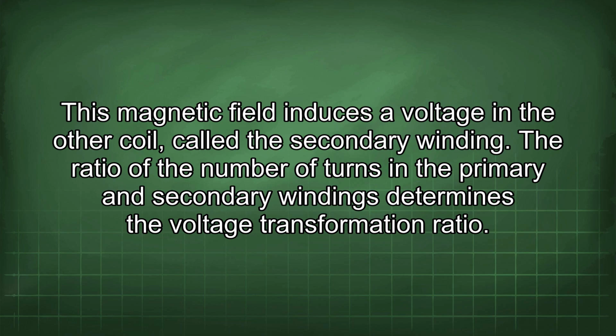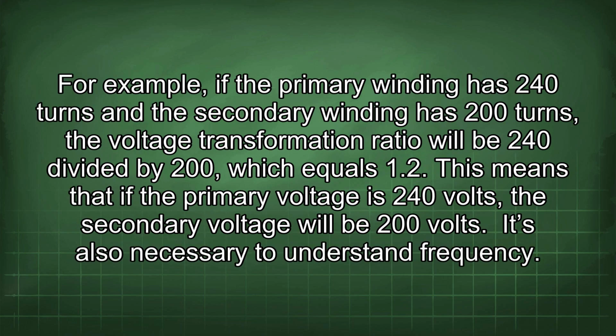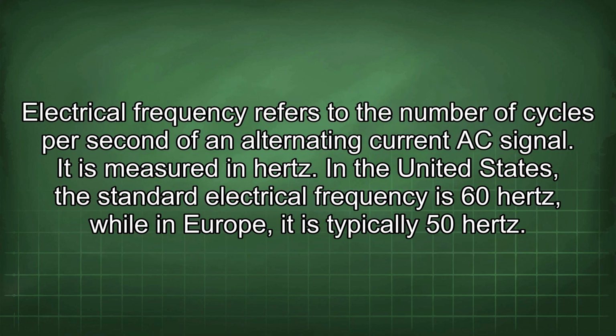The ratio of the number of turns in the primary and secondary windings determines the voltage transformation ratio. For example, if the primary winding has 240 turns and the secondary winding has 200 turns, the voltage transformation ratio will be 240 divided by 200, which equals 1.2. This means that if the primary voltage is 240 volts, the secondary voltage will be 200 volts. It's also necessary to understand frequency. Electrical frequency refers to the number of cycles per second of an alternating current AC signal. It is measured in Hz.